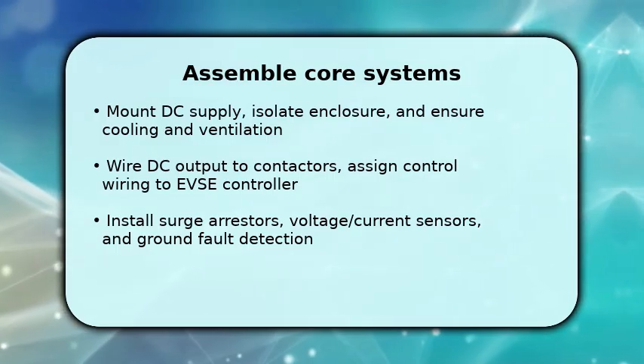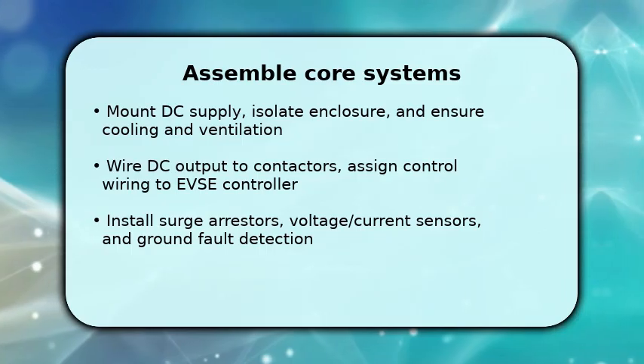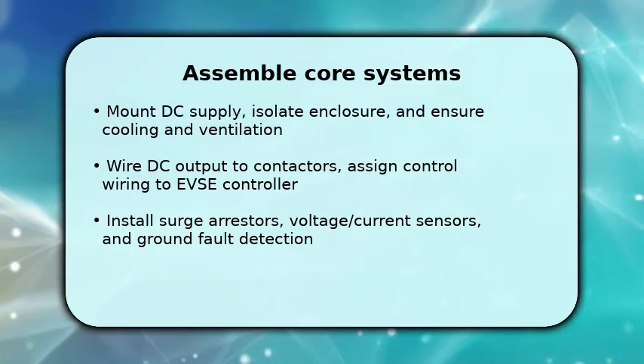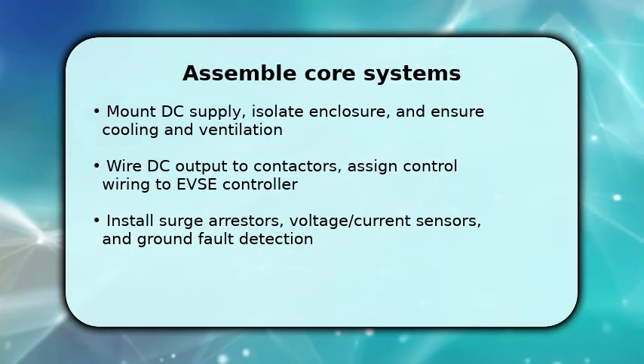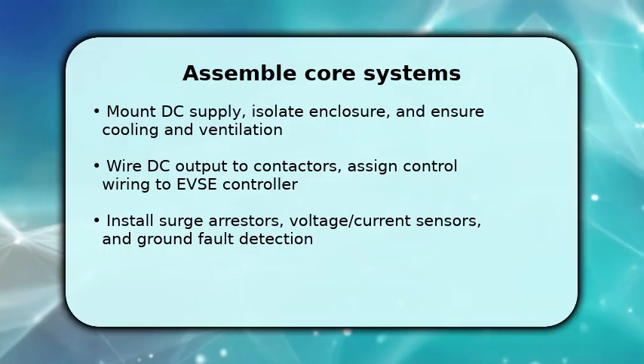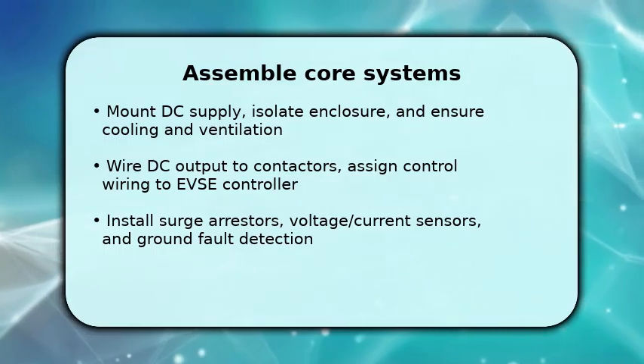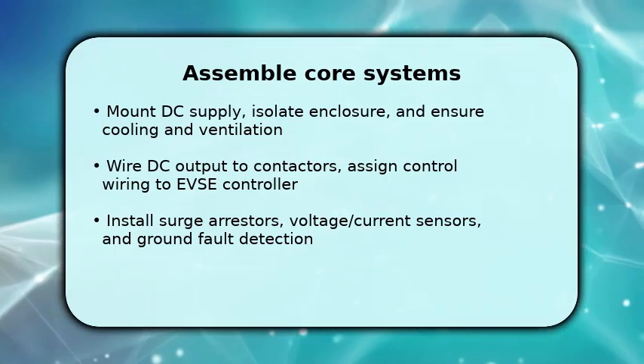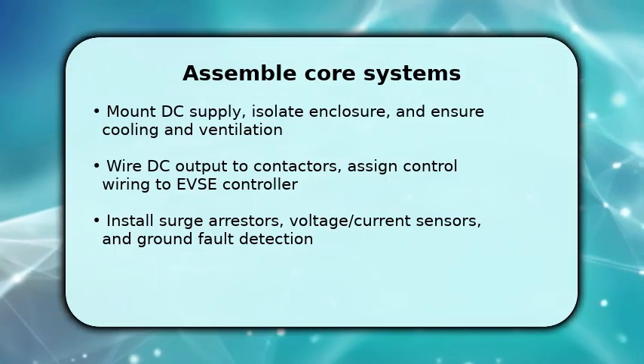Make control and power wiring in stages. Connect DC output through rated contactors and fuses, then route sensor leads, current, voltage, temperature to the EVSE controller. Integrate ground fault detection and an emergency stop circuit tied to the interlock.